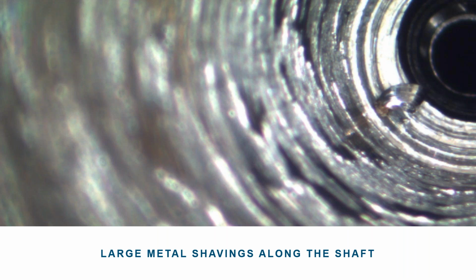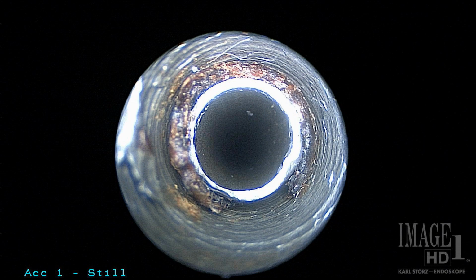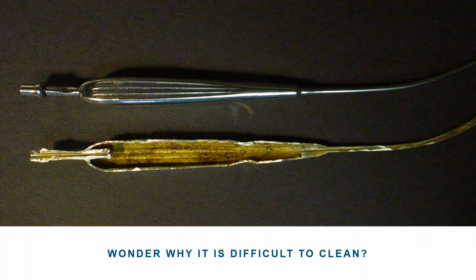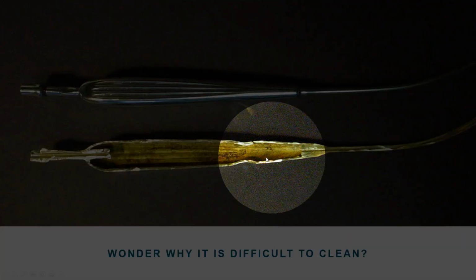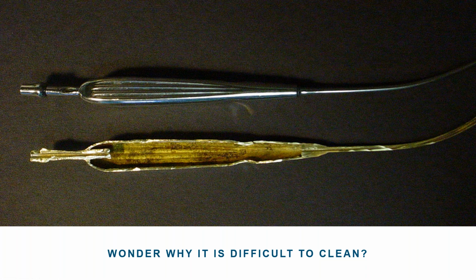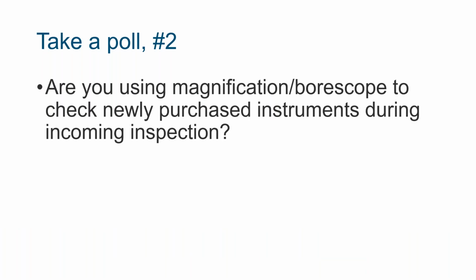What happened, I think, is that when they drilled it, it was hot enough to get the stock stuck to the body of the shavers. So it's important, when you purchase these instruments, especially the shavers, a $10,000 piece of equipment, to make sure that it is actually a good product. If you don't, over time you can see an accumulation of debris inside the suction tips. This was interesting: I put a borescope inside it and it was still showing debris. I cleaned it, soaked it for a long time, and it came back. I could not clean it, and debris was still inside. When I cut it open, you can see there are some issues. Later on we found out this should have been a disposable, one-time-use item, but it looked like the rest of the yankauer covers, and it was in use for a long time and never got cleaned. So these are the issues that we have.